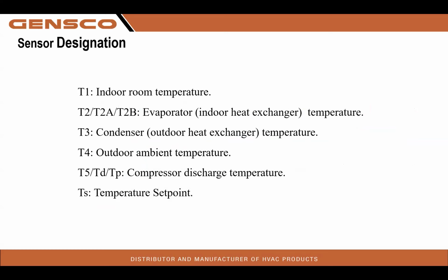Our sensors, as described earlier in the presentation: T1 is your indoor room temperature. It's basically sensing the return air temperature. T2, T2A, T2B, evaporator, indoor heat exchanger temperature. It is measuring the temperature at all times. T3 is a condenser, outdoor heat exchanger temperature. T4, outdoor ambient temperature.